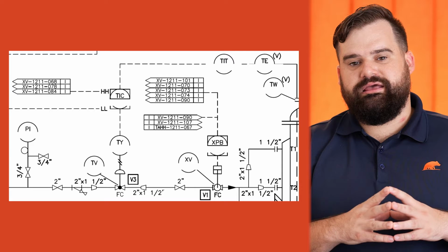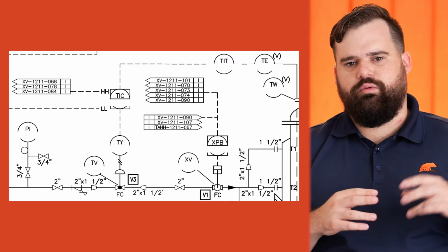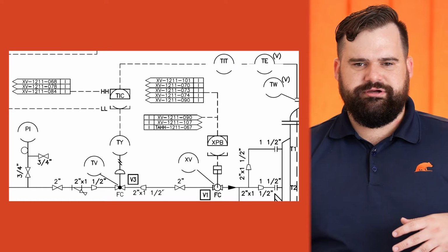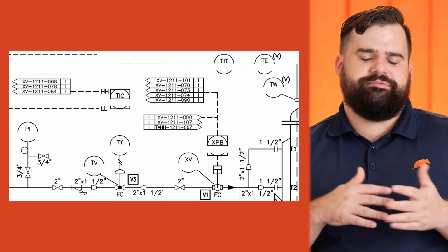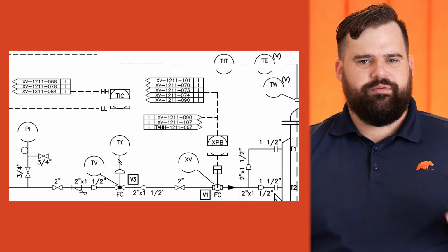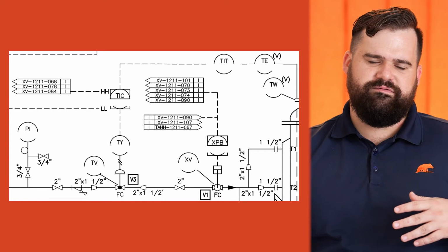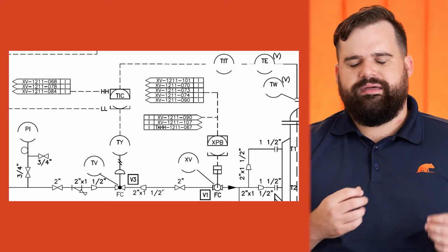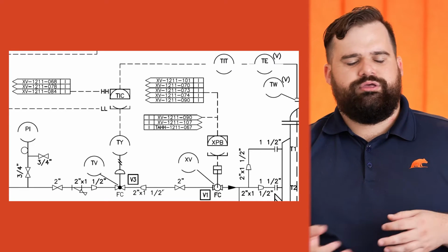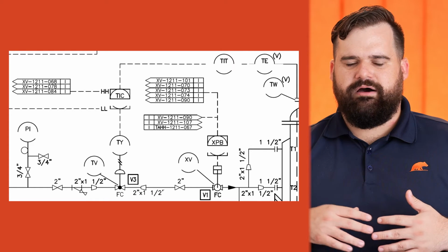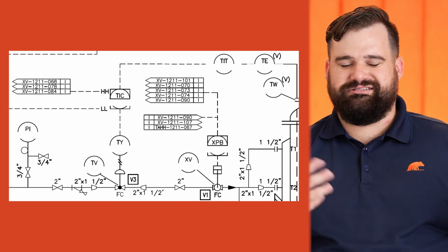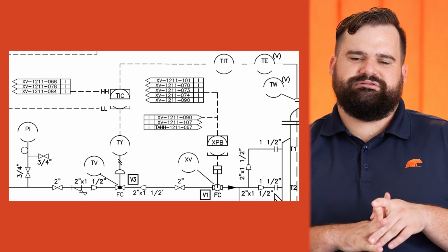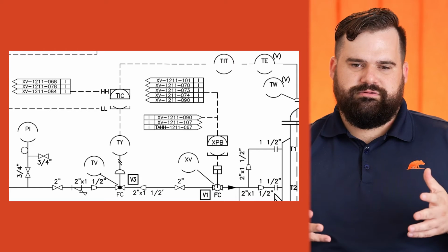So sometimes we can get more in depth with this, and we can say we don't want a DCS failure to also have a DCS trip. We want to have an SIS trip. We only want to use DCS trips for manual failures, or we want to have separate PLCs, so that's kind of taking it a step above. But on this very basis, you definitely don't want to use an element that's part of the initiating event loop. You may have some instrumentation guys that can tell you how instrumentation and controls that shut the same valve is independent. Just make sure you're having that discussion in your PHA about independence, right?